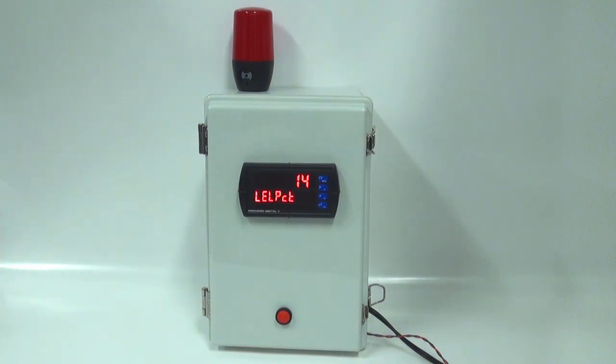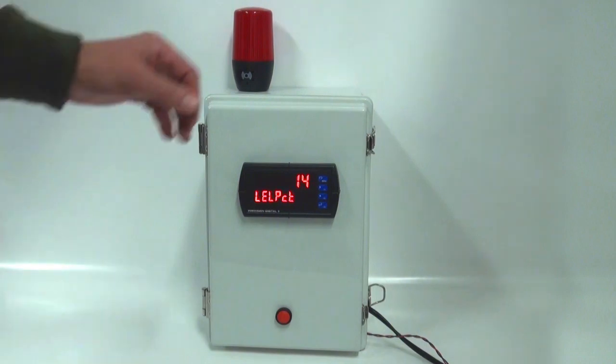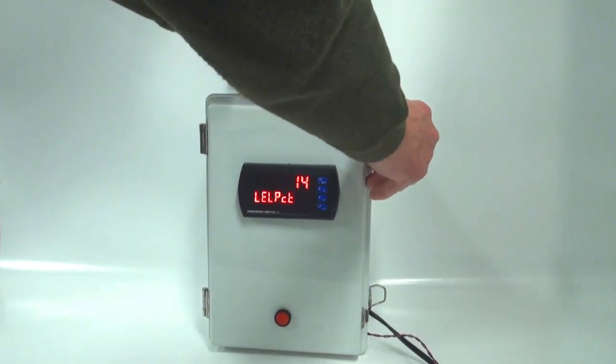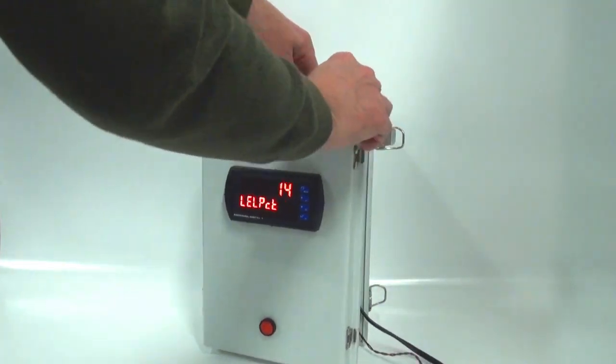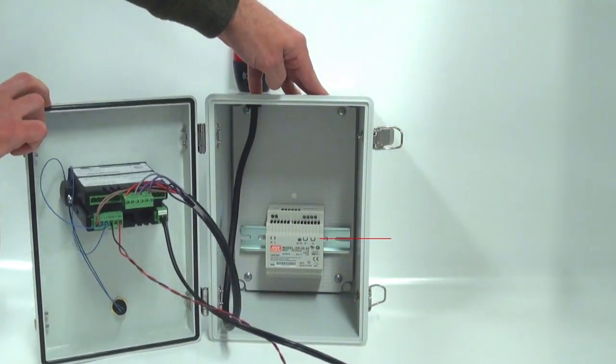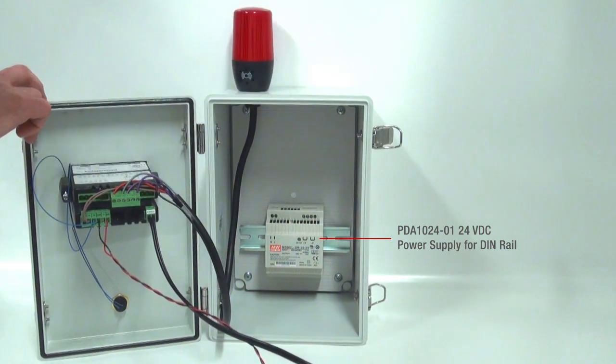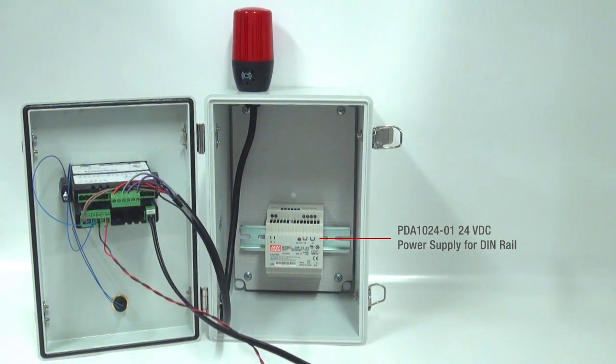In this particular application, some transmitters require more than 200 milliamps of power than the ProView can provide. So in our enclosure, we are offering an external 24-volt transmitter power supply that mounts right in the back of the enclosure. This power supply provides 1.5 amps of power, so you could install it right in the base of the enclosure and power transmitters that require more than 200 milliamps.